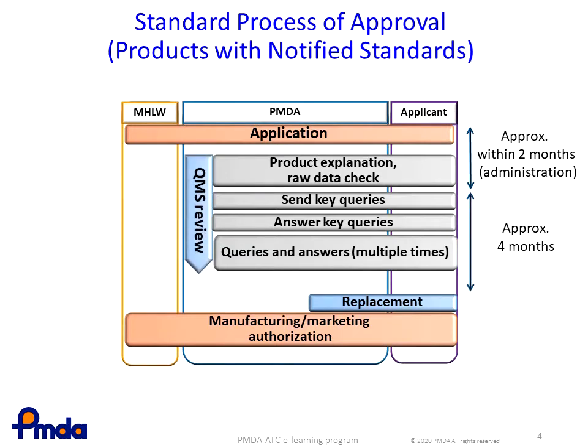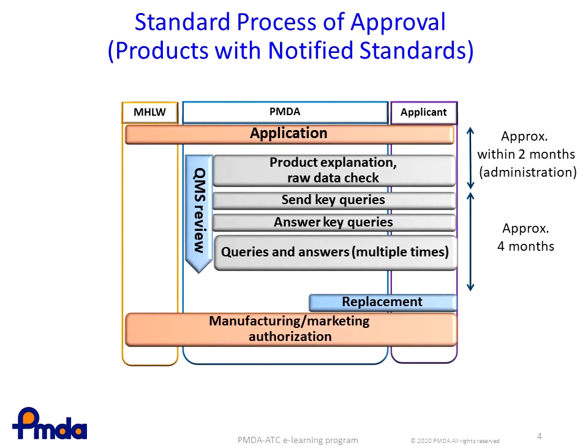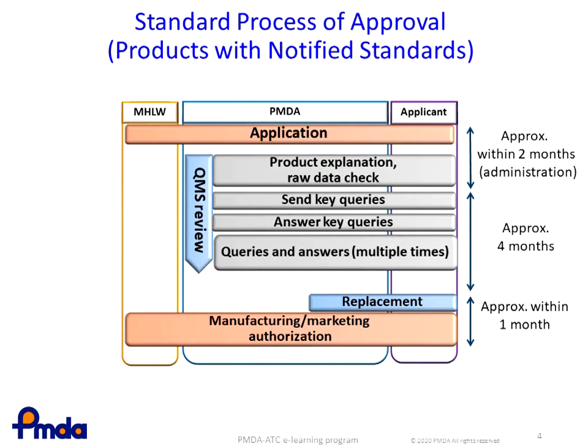A QMS review is conducted concurrently with document review and Q&A exchange. After discussions with PMDA, the applicant then resubmits some of the documents for review, and if they are acceptable, an authorization of manufacturing and marketing will be given within one month. Therefore, the total time from application to approval is seven months for ordinary products.